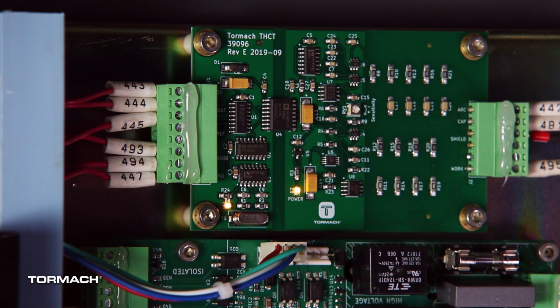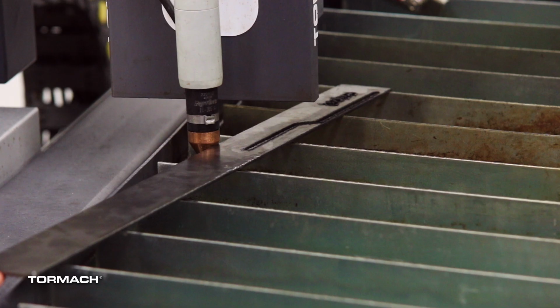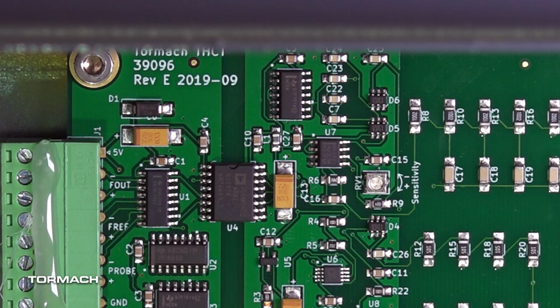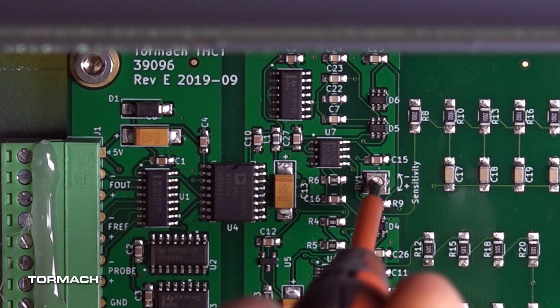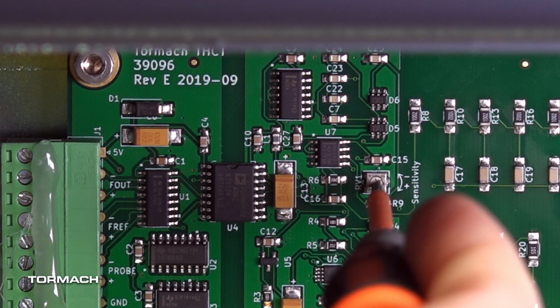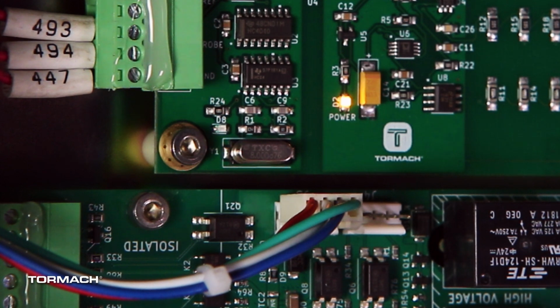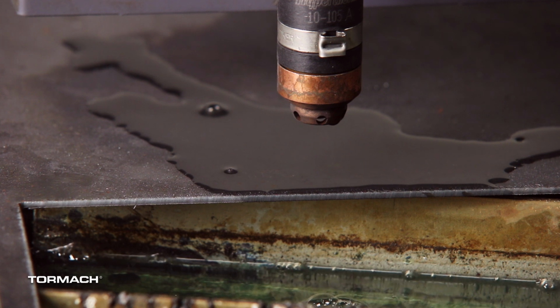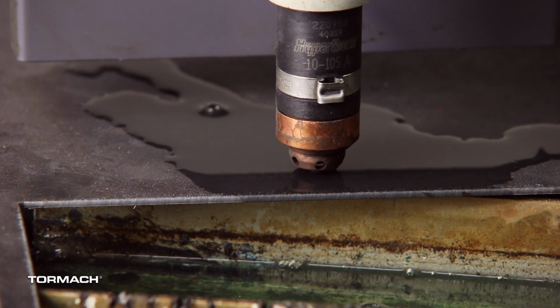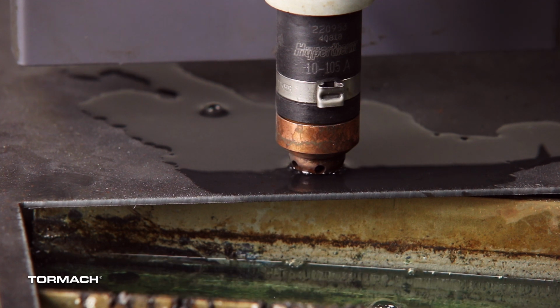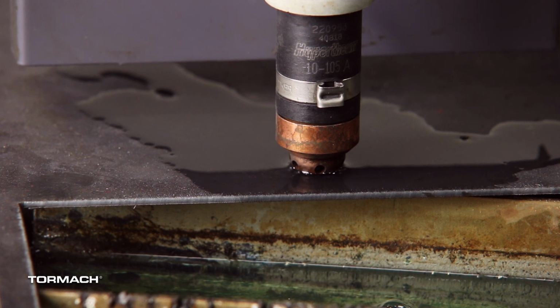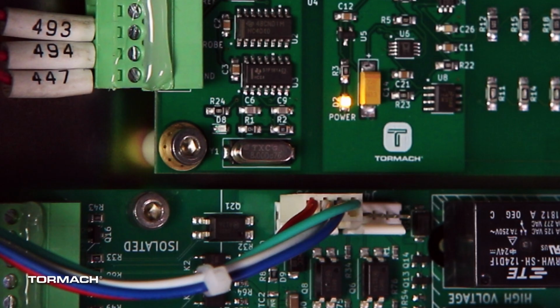This is signaling to the controller that the torch is contacting the workpiece. If the LED is not lit up, let's verify that our workpiece is touching the torch and that the ground clamp is connected. And then we'll go ahead and make an adjustment. When we dial this adjustment counterclockwise, it's going to reduce its sensitivity. So if our light is illuminated, it should shut it off. Then we'll turn it back to the right until that light just turns on. From here, we can jog the torch just above a piece of stock, and we'll splash some water on it so that we have the torch touching the water but not the workpiece itself. And what we want to verify is that that probing light does not turn on in this scenario.